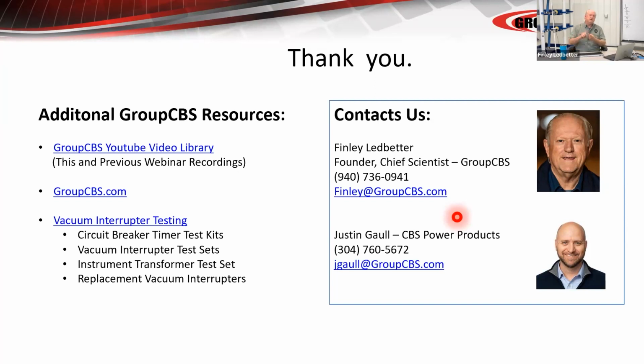Again, I'm talking about a piece of equipment that's clean, it's modern, it's well looked after, not in a dirty industrial environment that has a lot of airborne contaminants or salt water. Then you've got to be every year or two doing diligent maintenance, or if it's on an arc furnace breaker or something that's being used repetitively, because breakers are designed for 1,000 operations between major maintenance. Major maintenance means the breaker's torn completely apart in every piece. So they're not designed like a contactor or a switch for tens of thousands of operations. So as long as you've got one good, credible primary injection test in the not too distant future, I wouldn't hesitate to secondary inject test, but I would make sure certainly your critical breakers get out for primary injection every 5 years.